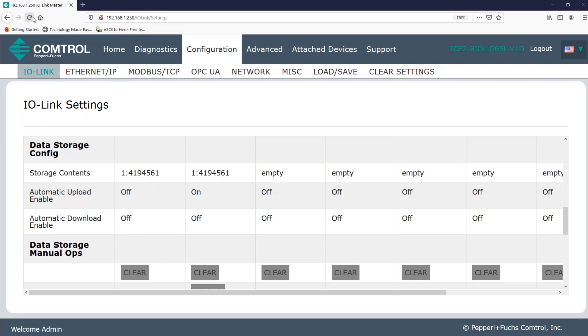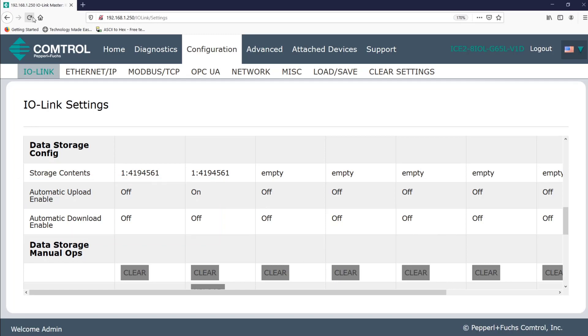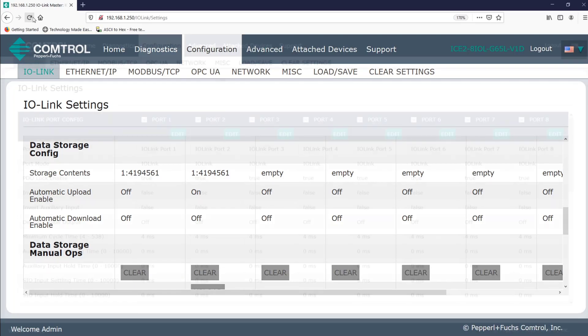And as a side note, don't turn on both automatic upload and automatic download. You'll likely get mixed results between different manufacturers. And if the upload download buttons aren't displayed, your device may be older than version 1.1 and data storage may not be an option. So by this point, you should start to see how easy it is to replace a defective IO link device or configure multiple devices with the same set of parameters.